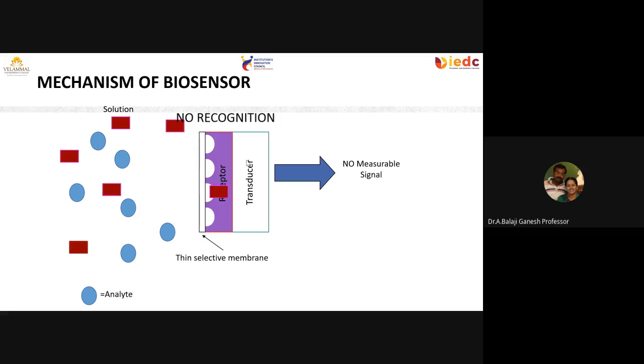I can have the same transducing element as the thermal sensor. Instead of glucose oxidase, I can use urease. Urease is another enzyme which would interact with the urea concentration present in your urine sample and produce a certain level of thermal changes, temperature changes, enthalpy changes. That enthalpy would be recorded through this thermal sensor, and the corresponding resistance change would be recorded, directly proportional to the amount of urea present in your urine sample.